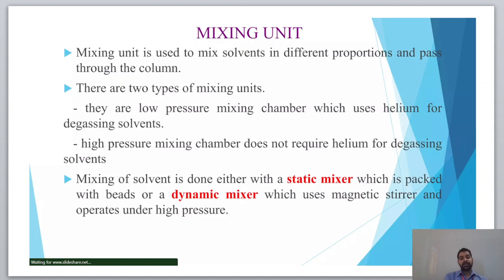Next, high pressure mixing chamber does not require helium for degassing solvent. Mixing of solvent is done either with a static mixer, which is packed with beads, or a dynamic mixer, which uses magnetic stirrer and operates under high pressure.